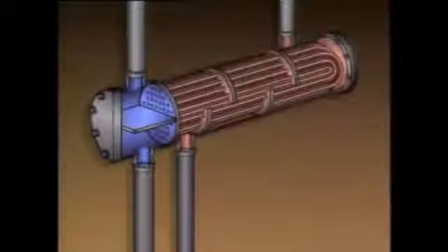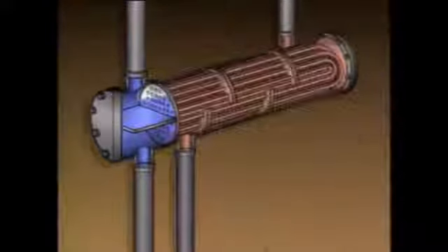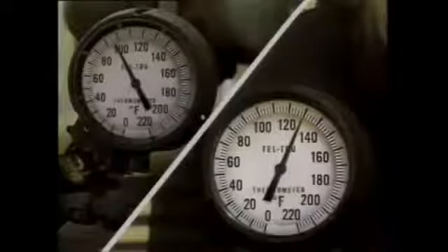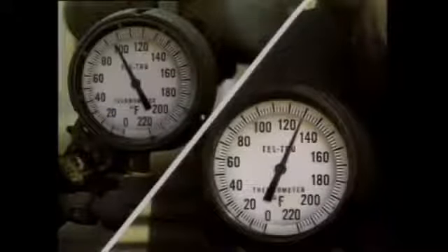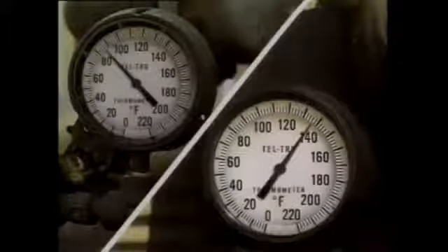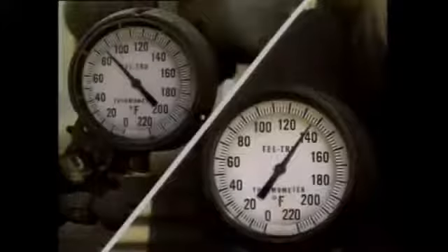No matter how air or other gases get trapped inside a heat exchanger, they can cause it to become airbound or vapor-bound. There are several symptoms to indicate this. For example, when trapped gas blocks flow to some of the tubes, the outlet temperatures of the two fluids may change. This is because the gas is restricting flow into the tubes, and the restricted flow causes less heat transfer surface area to be available. The decrease in heat transfer surface area will cause the outlet temperature of the process fluid to increase, since less heat will be removed from the fluid.